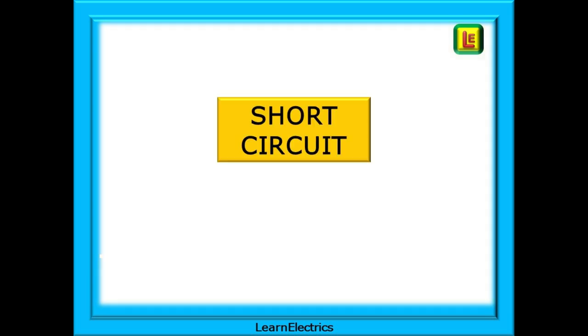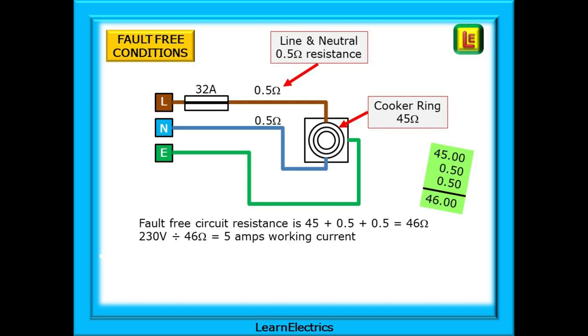A short circuit is completely different. Let's look at this. In this example, we have a cooker circuit protected by a 32-amp protective device. There are no faults on the circuit. Looking at just one cooker ring, we see that it has a resistance or impedance of 45 ohms and each of the line and neutral conductors has a resistance of half an ohm. Current flows along the line conductor, through the fuse, through the cooker ring, where it loses its energy as it makes the ring hot and then flows back along the neutral. Using Ohm's law, we can calculate the current flowing. 230 volts divided by 46 ohms gives us a current of 5 amps, far less than the 32-amp breaker. All is okay.